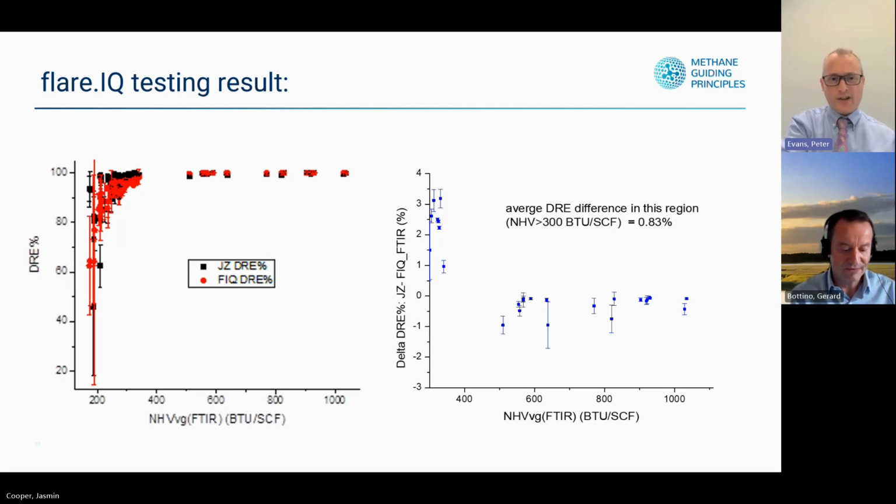But what you can also see on here is why these sorts of measurements are so important. The x-axis on the bottom of the graph is plotting the composition of the gas, and the destruction efficiency is on the y. And if you could plot this and show this in 3-dimensional space, you would also have to be thinking about flare volumes and also critical environmental effects like wind. And what you can see is you can go from very high levels of efficiency in excess of that historic 98% figure that people have used, down into very low destruction efficiencies very rapidly.